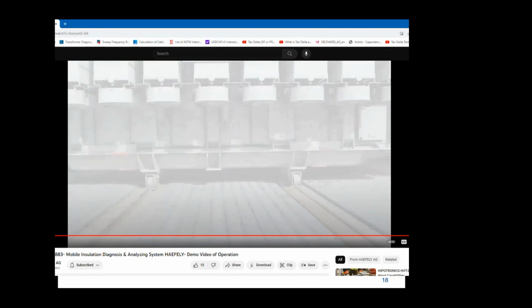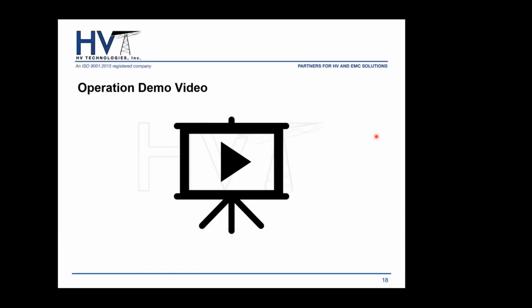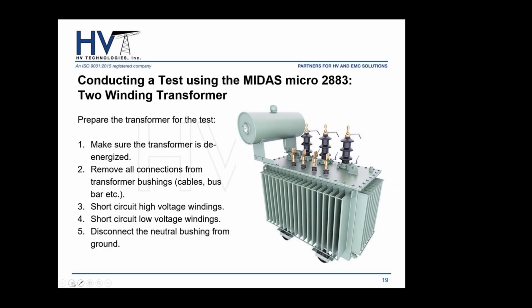That video basically recaps everything that I mentioned up to this point. And as you can tell, it's quite simple. It's very hassle-free. So next, before we go into questions, I want to do just a quick review of an example for a two winding transformer like you just saw. Like we mentioned, we want to short the high voltage and low voltage. If you have a neutral bushing, you will disconnect that from ground and then short it with the other bushings, and then you can go ahead and start your measurement.